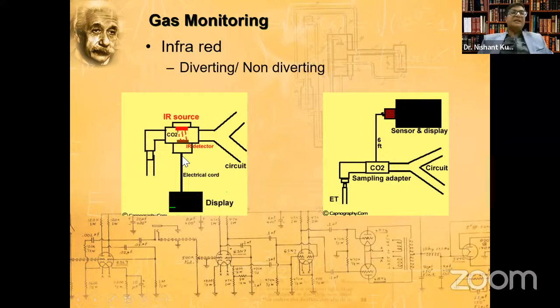Each gas has an ability to absorb a particular wavelength, right? So there are different wavelengths which are emitted. If it's CO2, a different wavelength is emitted. If we are monitoring the halogenated gases, we have different wavelengths. Now, an infrared source is usually used for gases which have dissimilar atoms. So carbon dioxide, halogenated agents, nitrous oxide, all these can be measured, but not oxygen. It's a single atom molecule.